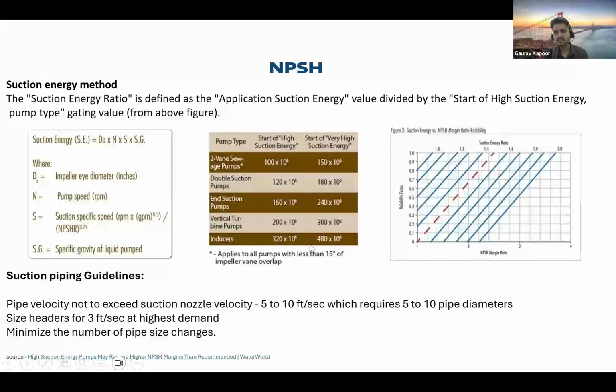But that does not stand for large size district cooling plants where the flows are very high, because the suction energy ratio or the suction velocities are so high that a difference of NPSH-A versus NPSH-R of 2 or 1 meter does not work out. We have done this exercise for more than 20 to 25 plants in the last 5 years, and now as a standard for large size DCS, they say the ratio between net positive suction head available to net positive suction head required is minimum 3 to 4 times, so that cavitation does not happen.